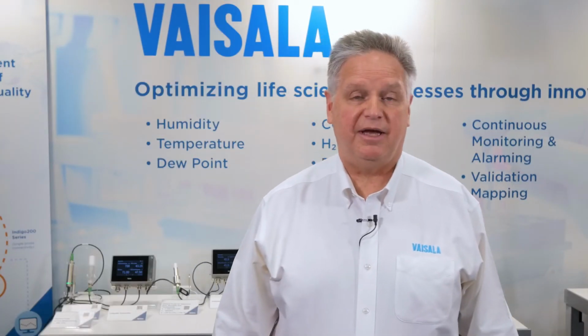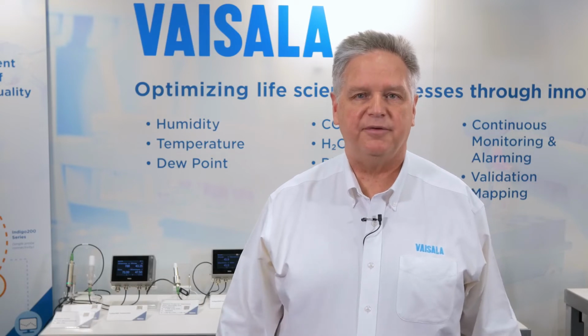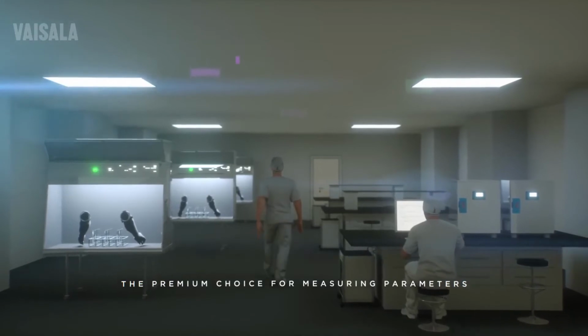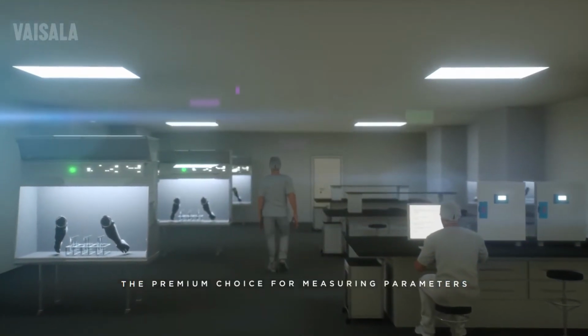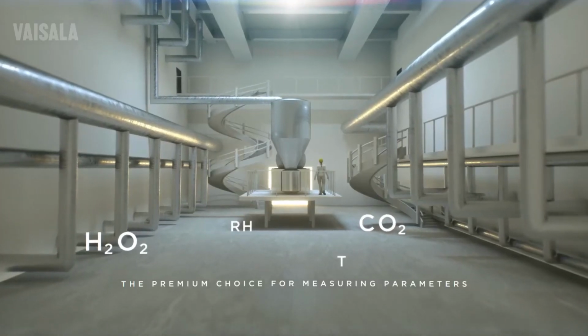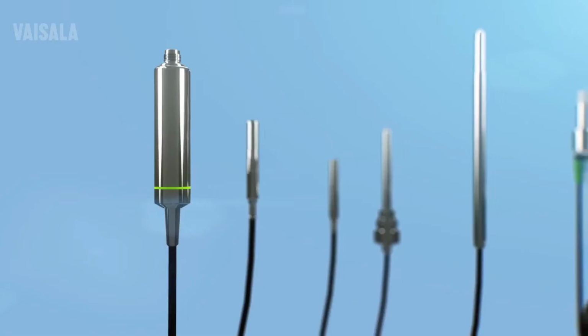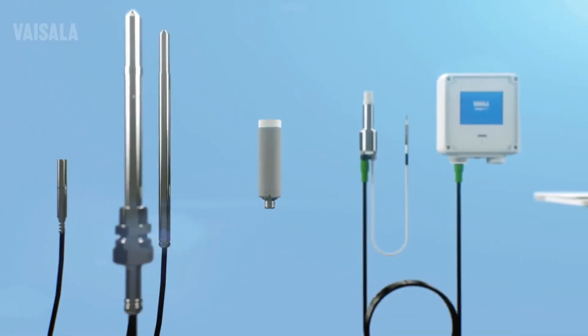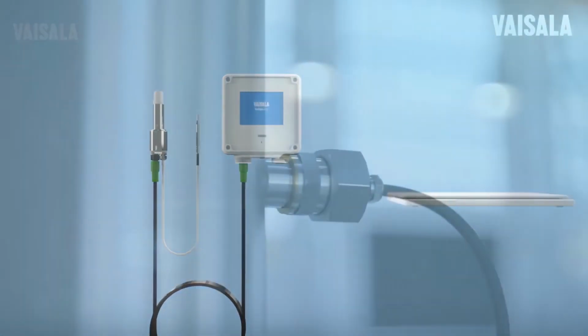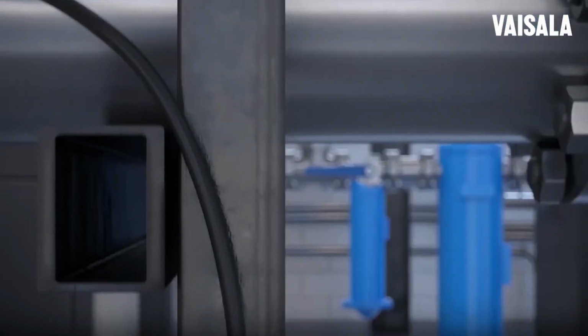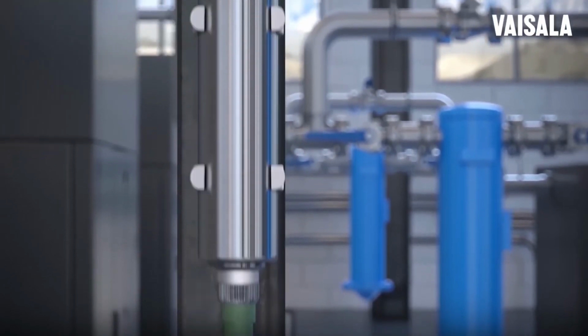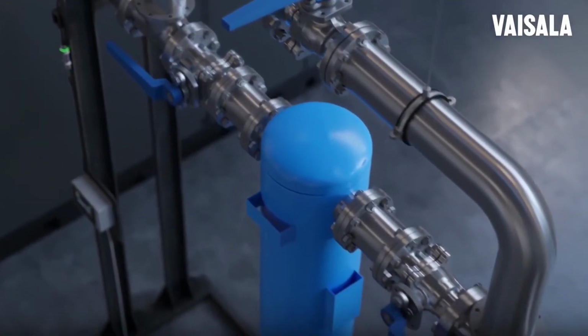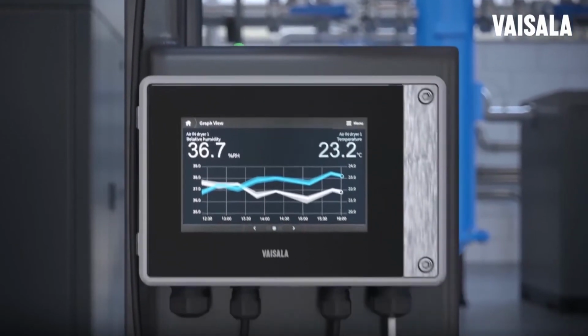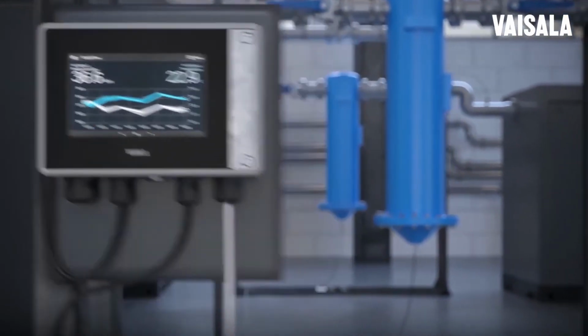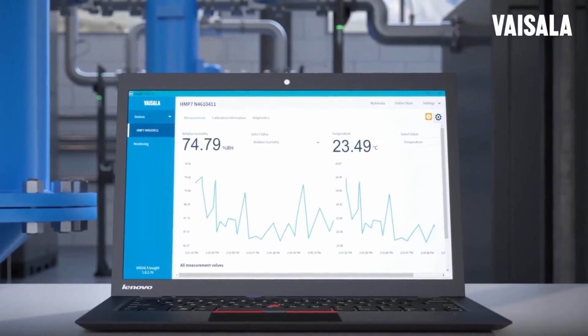The Indigo is a modular platform, so a couple of the examples that we can talk about briefly here. The most common one is tissue and cell growth incubators, and in those we're measuring the conditions of relative humidity, temperature, and CO2. Those parameters are critical to cell growth and cell culturing. That work is done to do testing, in vitro fertilization, and research. And having all three parameters tied into one Indigo device allows the customer to connect them all to one piece of equipment to display those parameters, data log those parameters, and be able to monitor those over a long period of time.